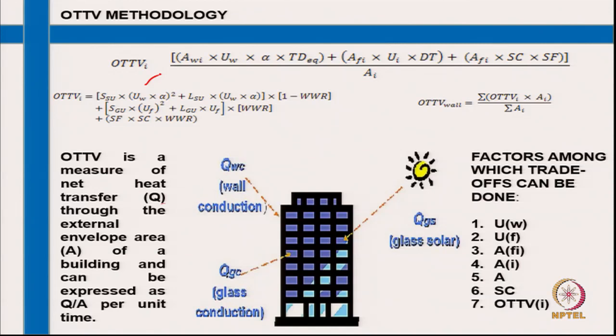For the ith wall you can find out the U value you have chosen, the absorptivity, TD equivalent temperature difference, and area. That is for the solid portion of the wall. This is for the fenestration, etcetera. So this is the total thing divided by the area.